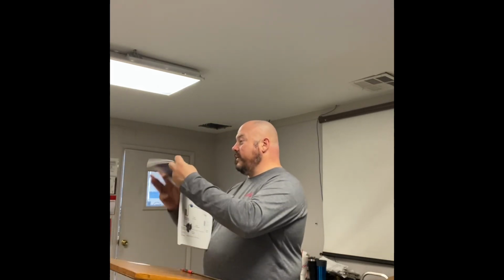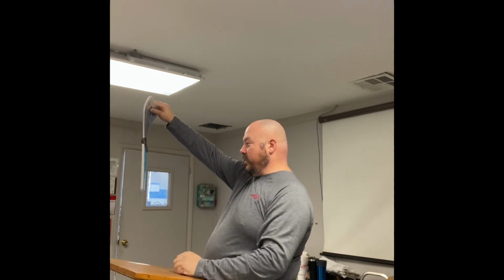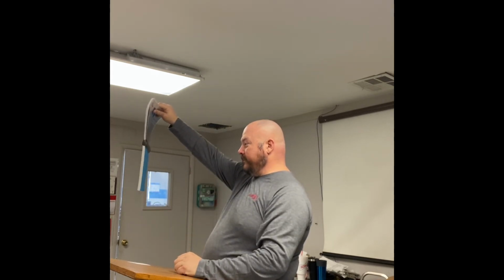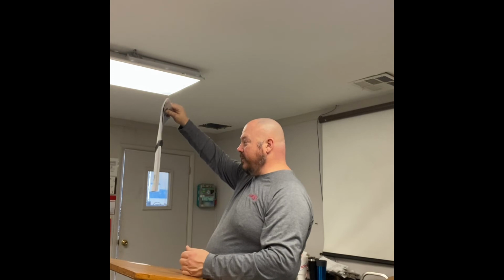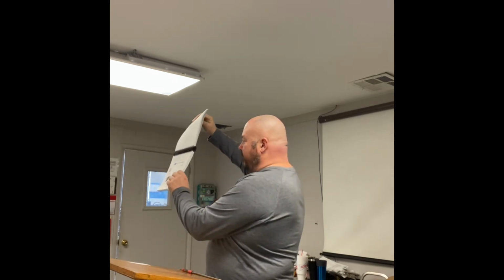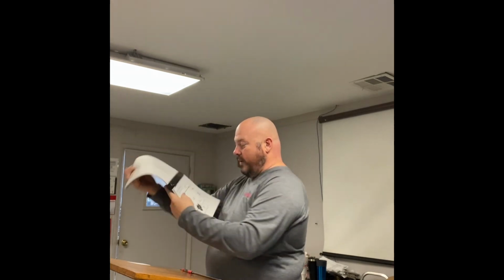If the system has a sight glass, almost all refrigeration systems will have a sight glass. Look for moisture, right there. You should also see it completely solid with liquid with no bubbles. Any question where we're at? We're looking at this picture. Okay, you got that one? It's about 2/3, there you go.